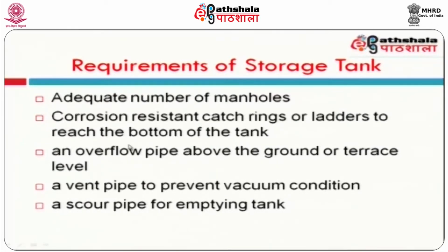Otherwise, without a vent pipe there will be vacuum created inside the tank during distribution, which will lead to cracking of the side wall and finally leaking of water. And also a scour pipe; the purpose of the scour pipe is to clean the tank. Periodically, once in a month, the storage tank is to be cleaned to eliminate any deposits, for which a scour pipe is provided at the floor level with a valve. The valve is opened at the time of cleaning, and then the tank will be cleaned.